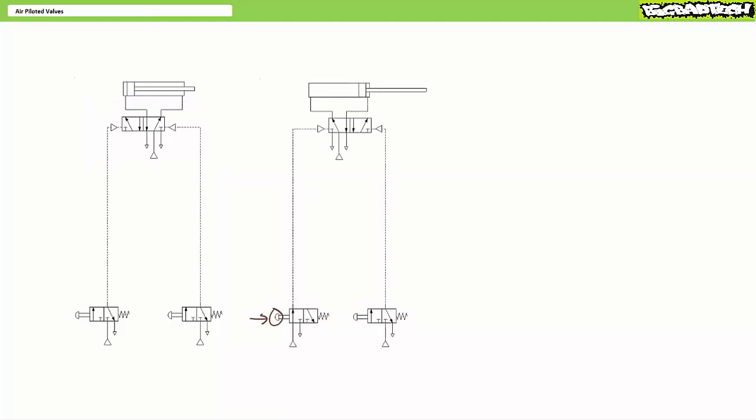When an operator presses push button one on the left, it sends a tiny puff of air to the air pilot on the left hand side, shifting the air piloted valve into a position such that pressurized input port one is routed to actuator port four and actuator port two is vented to exhaust port three. Given negligible losses in the short primary lines, the cylinder extends with undiminished strength and speed.